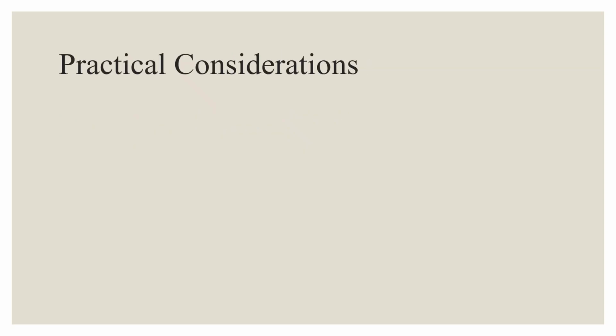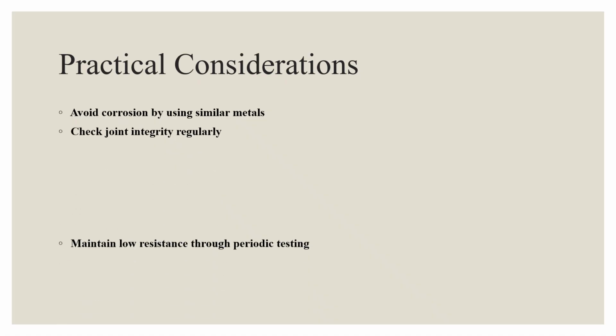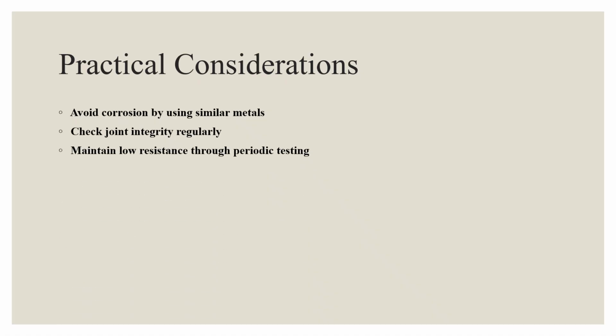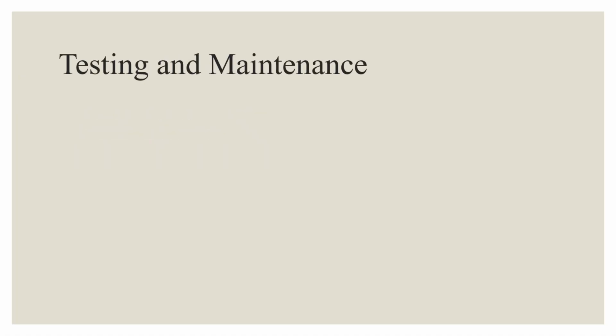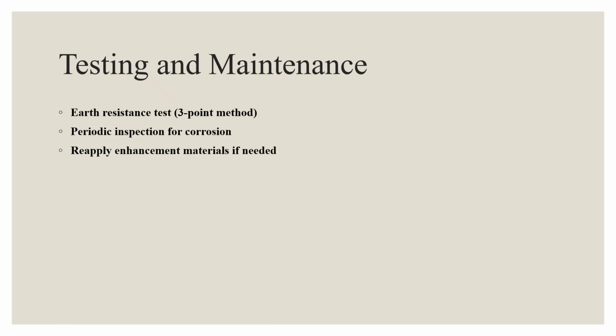We also have some practical considerations. So in practice, it's also important to avoid corrosion by using similar metals, check joint integrity regularly, and maintain low resistance with periodic testing. A well-maintained grid remains reliable throughout the life of the substation. We also have to perform testing and maintenance. We perform regular earth resistance tests using the three-point method and visually inspect connections for corrosion or damage. Enhancement materials like bentonite may need to be reapplied periodically to maintain the performance.